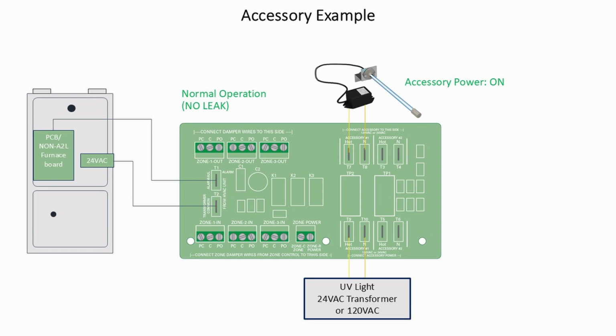Here's another accessory example using a UV light. The UV light would connect to accessory 1 terminals, hot and neutral, and the UV light power would run from T9 and T10 accessories with 120 volts out to run either a 120 volt or a 24 volt transformer, field supplied, mounted outside the furnace cabinet, for power to the UV light.